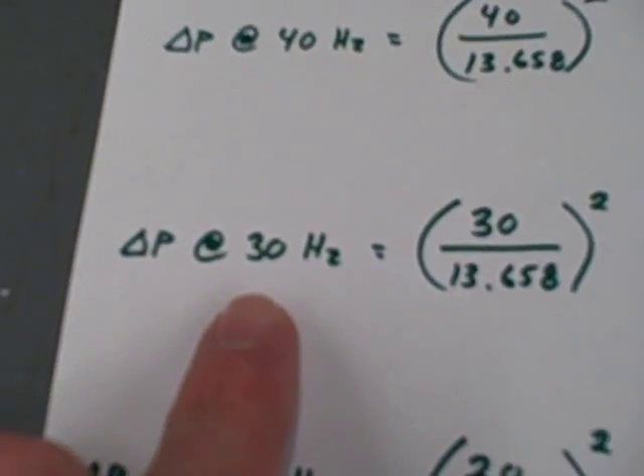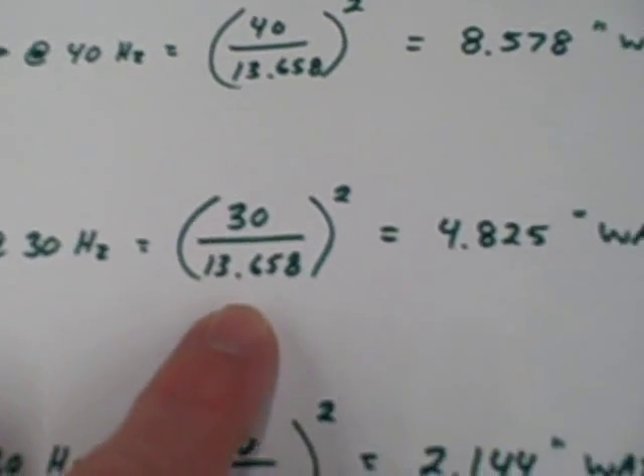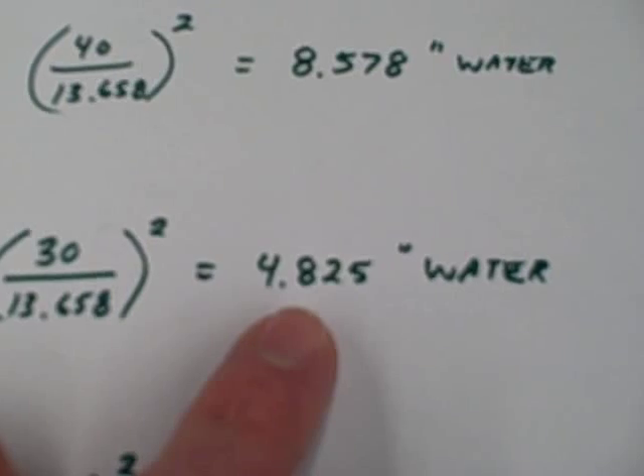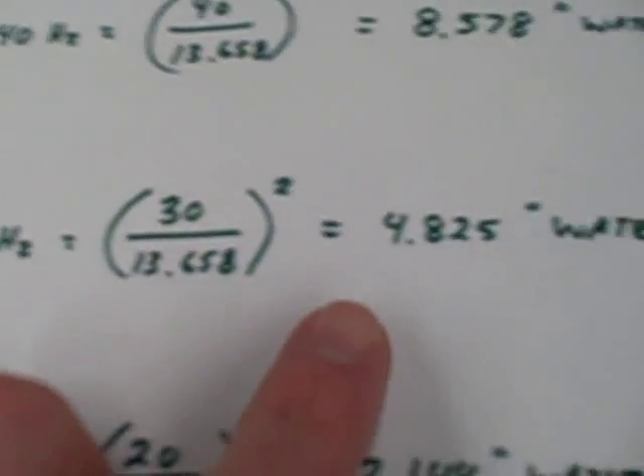Moving down to our next test point, we're going to lower the motor frequency to 30 hertz. Using the k-factor we calculated previously, we calculate a differential pressure of 4.825 inches of water. So we're going to decrease the motor speed to 30 hertz and see how close to that value we get.